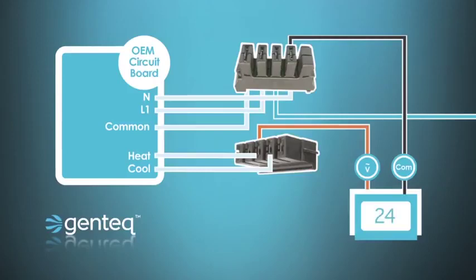And now again, I need to turn the power back onto my system, give my thermostat a call for heat or cool, and wait for the circuit board timing to send that voltage down to the heat or cool wire. And if that 24 volts shows up, then I know I've got the proper input to the motor to tell it to turn on from that thermostat demand, whether it be heat or cool. So if I've confirmed that that tap is a programmed tap in the motor, and that I read 24 volts between that wire and common, that means that I have the voltage I need going to the motor to tell it to turn on.